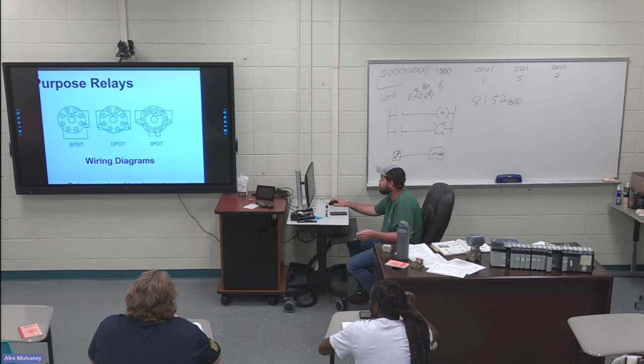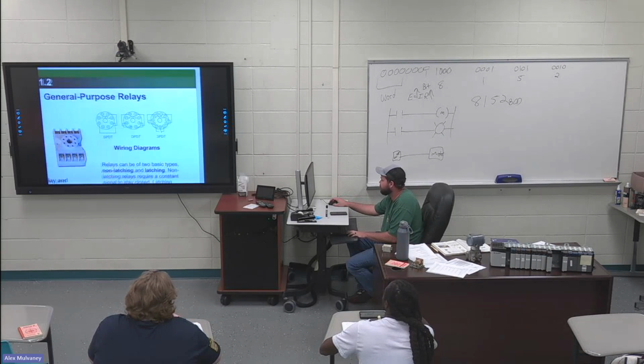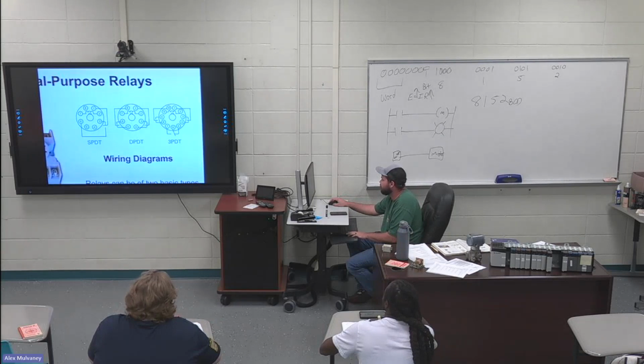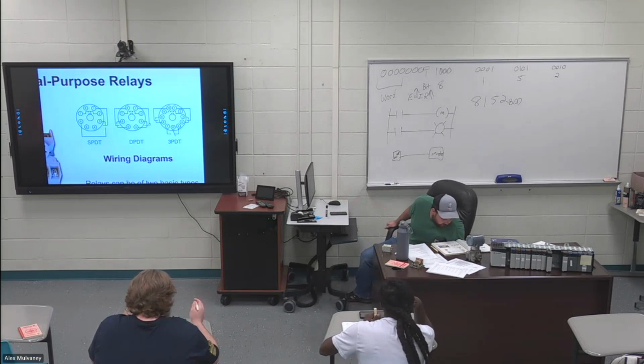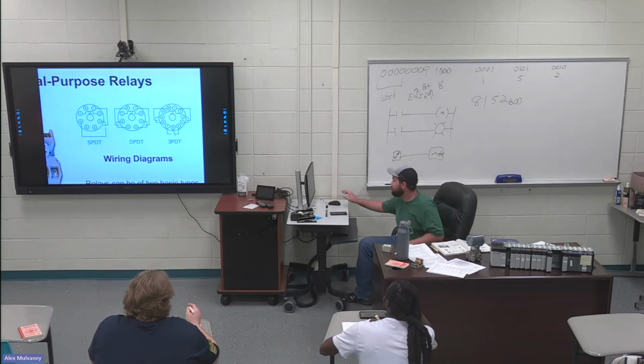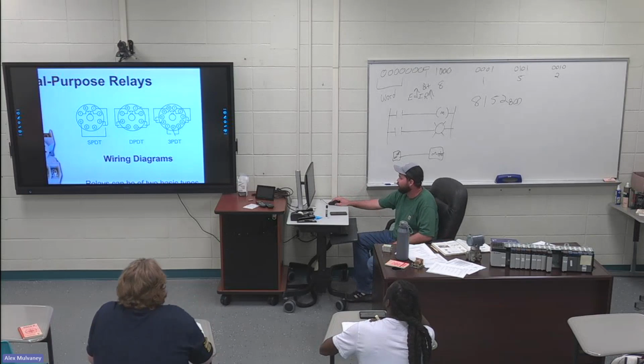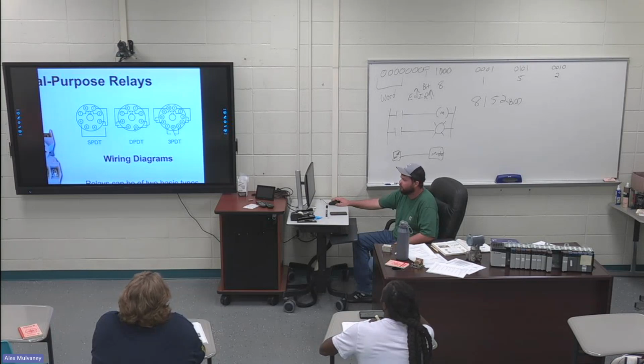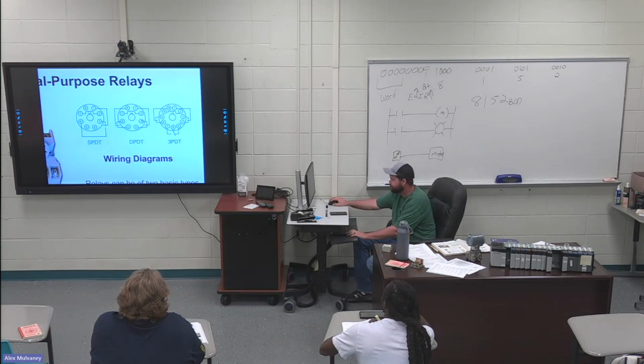That's not supposed to be like that. 3 is supposed to be open. Yeah, 3 is supposed to have a gap right there. Does that have a gap in the book? Well, there should be a gap between 3 and the one coming from 1. Like 1 to 3 should be a normally open, and then 1 to 4 should be a normally closed. Does that make sense to everybody? So you have 2 sets of switching techniques. So you can turn stuff on and off with just turning off 7 and 2.